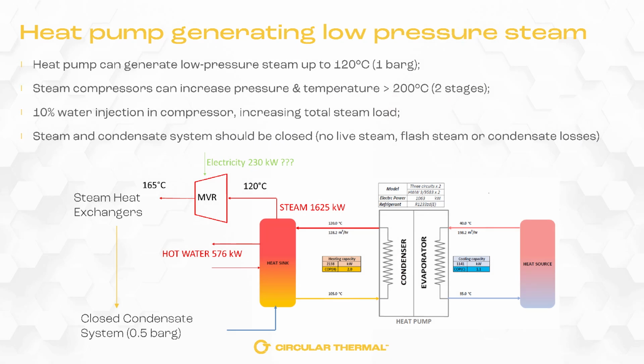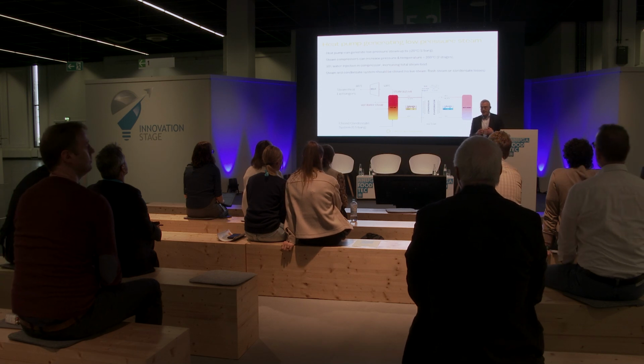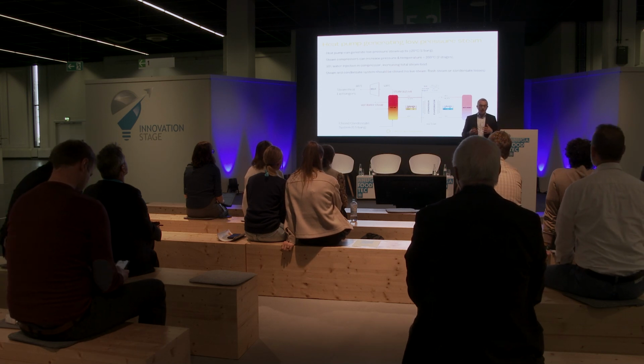For certain applications, steam is needed, and generating low pressure steam at about 1 bar brings us again into steam territory. Compressing that steam with an MVR system, with a steam compressor, is probably the most efficient way—these steam compressors are relatively efficient. That creates a secondary loop, which is not an open loop, it's a closed loop, with a heat exchanger, condensate, and flash steam.